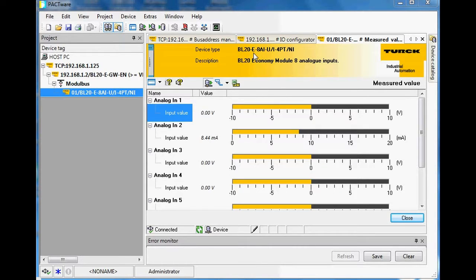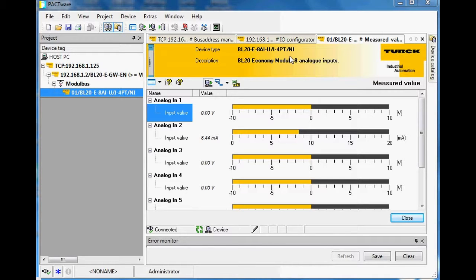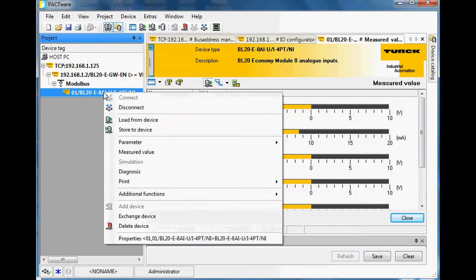Currently I can see I'm using channel two, and it's got 8.44 milliamps coming into that channel. This card is the BL20-E-8AI-U-I-4PT. It's a cool card because each channel can be an analog voltage input, or you can use two of the channels as a thermocouple or PT-series analog input as well.